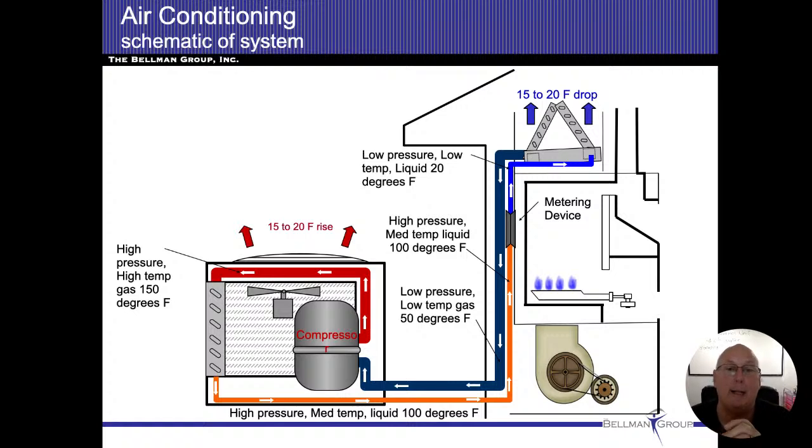If you look at this carefully, you'll see that the compressor, and I'm not talking about the fans that blow the air over the coils, the compressor is really the only moving part of the air conditioner. So as I'm adding pressure into the system, I'm also releasing pressure at that metering device. And those things are supposed to be in tune perfectly. So when the system is fully up and running, as I continuously add pressure to the system, the metering device is continuously releasing the same amount of refrigerant so that I can get that equilibrium of pressures. My change of state, going from a liquid to a gas or gas to a liquid, is what I was looking for.